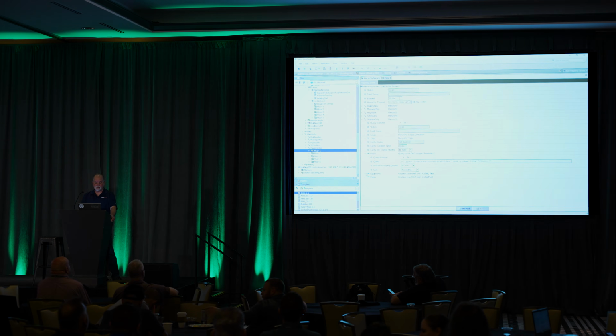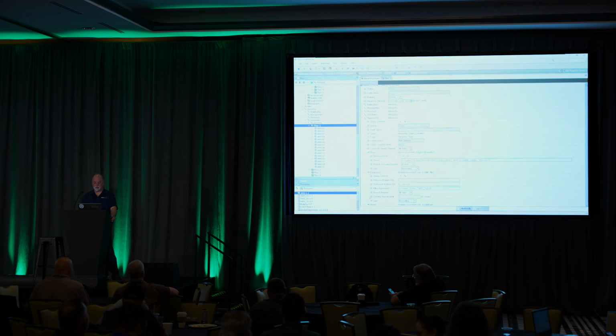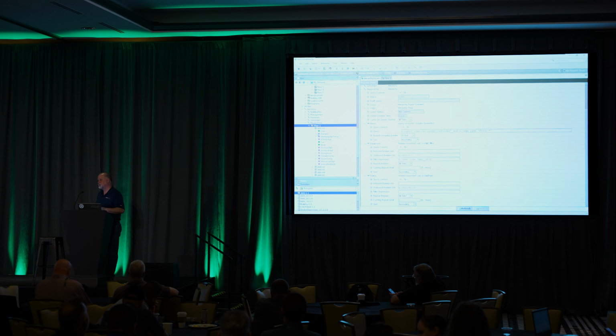And from there, I can just say, again, Niagara tags. I'm just looking at my child tag and looking for things that are named AHU something, and that's going to show up my air handlers beneath that. And then I can just say, I want to see the child points under that piece of equipment, and there's all the points associated with it. So I could copy this into any station, though I might need to tweak it a little bit. Maybe it's a BACnet folder instead of a LON folder. But without me having to do a whole lot of extra work, I could just put this on every job and it would build out dynamic navigation for me. I don't have to go build a nav file. It just reacts to what's there, okay?